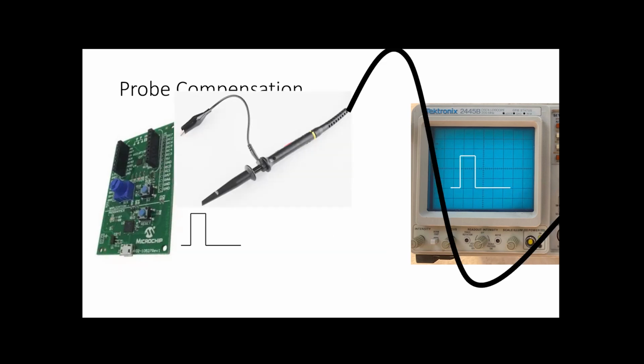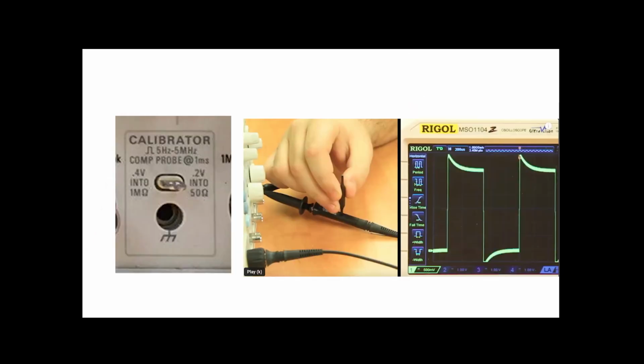So I use a scope probe. And if I use a scope probe, as long as the scope probe's set up properly, then I will get the signal that represents what's coming out of the device under test. Now, in order to set the scope probe up, somewhere on the front of my oscilloscope, there's a little thing called a calibrator. And what I do is I put the scope probe onto the calibrator, and I use a little non-metallic screwdriver, usually comes with the probe. There's a little variable capacitor inside the side of the probe. By twiddling it, I can twiddle it until I've got a square wave. You can see where that one there is still needing a little bit of adjustment. It's overshooting both high and low. So I've got to twiddle it a wee bit more till it turns back into a square wave.